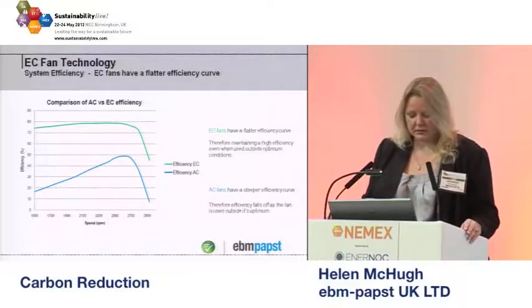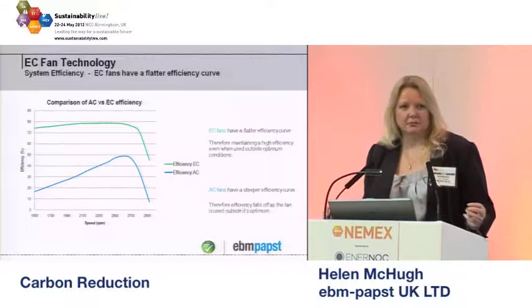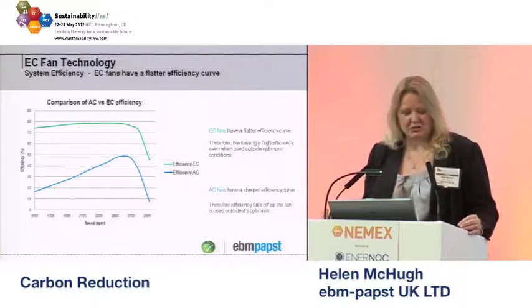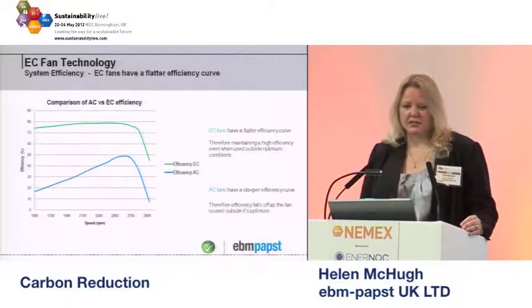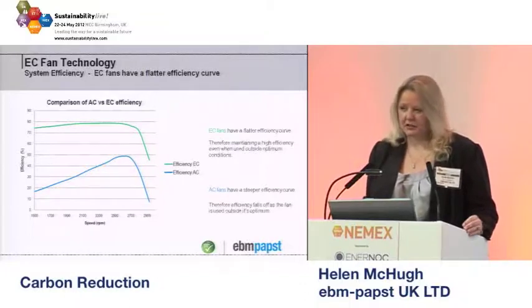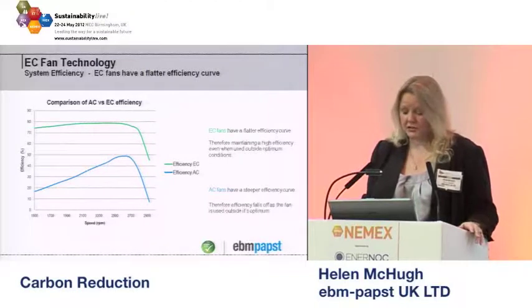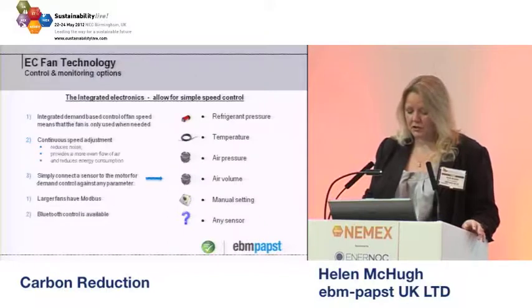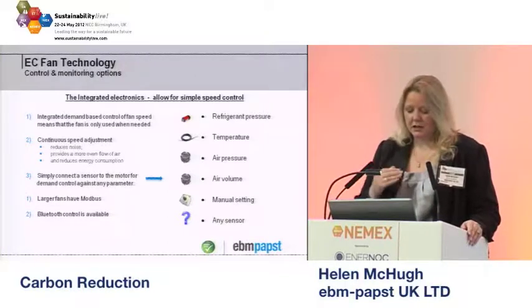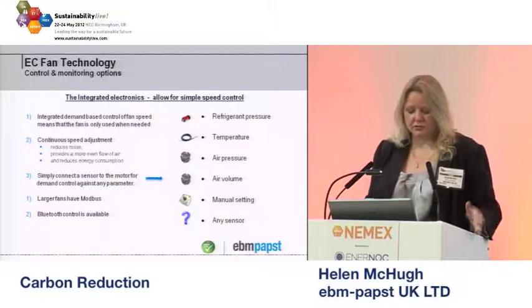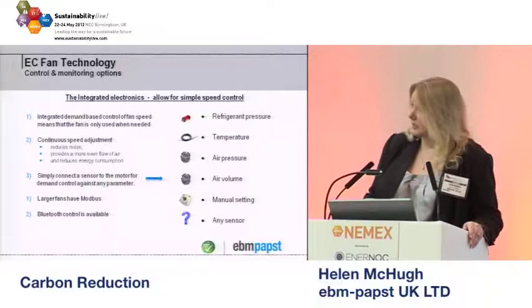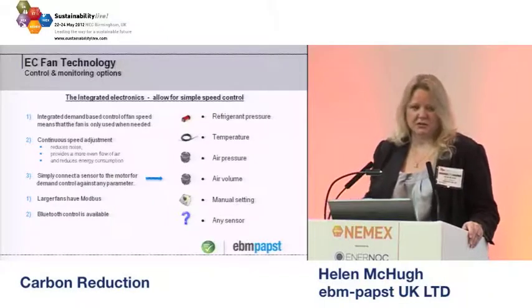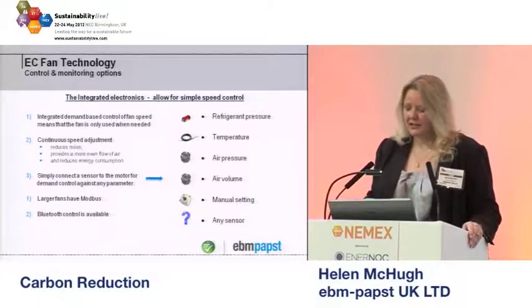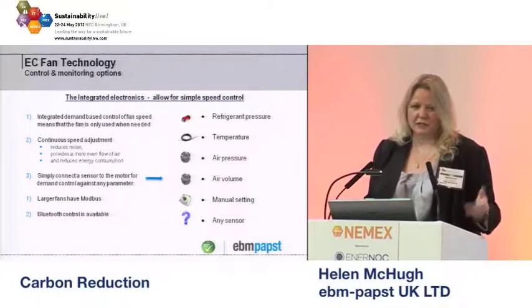This also just explains some of the differences in peak efficiency. And again, I don't want to get into too much detail, but it's important to know that using an EC fan, the energy efficient fan, allows you to optimise in your particular application, and you won't lose efficiency as the pressures change, for instance. But I want to get on to talk about the case studies. This just looks at some of the control that you can have within the EC fan. So anything you can imagine really, whether it's a temperature sensor, a CO2 sensor, that can be linked into the fan and it will regulate itself.